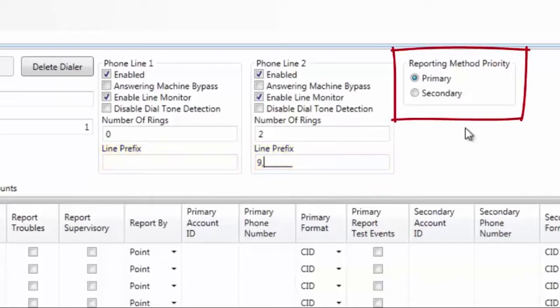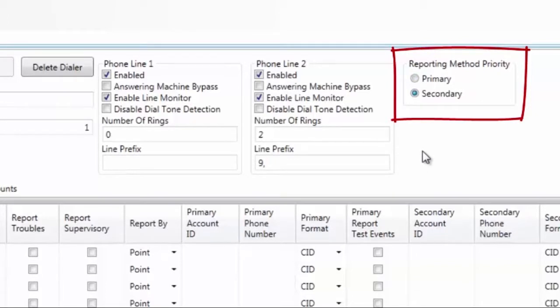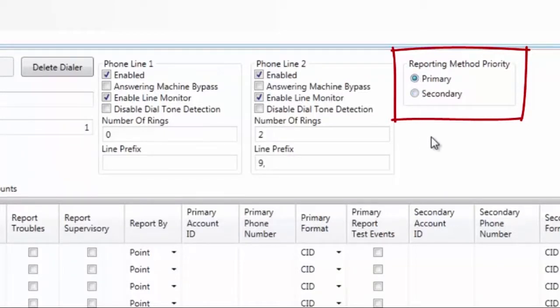Moving now to the reporting method priority. Your options are primary and secondary. The default is primary. These panels have the ability to communicate via a dialer, which is what we're working on currently, the UD1000, and or the IP communicator. If you would like the UD1000 to back up the IP communicator, you would set this to secondary, and when we get to IP reporting, we would set that to primary. You can also have the IP back up the dialer by setting this to primary and the IP to secondary.